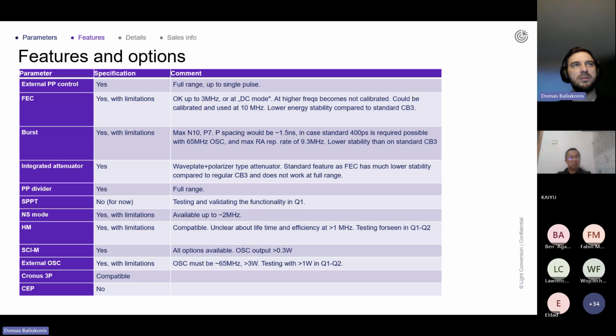It's basically the fast attenuator, and with the fast attenuator you can control every single pulse in the full scale. But in this 10 megahertz model, it's working up to 2 or 3 megahertz. Yeah, up to 3 megahertz. At higher frequencies, the calibration of the attenuation becomes unpredictable, so it's not usable for the user.